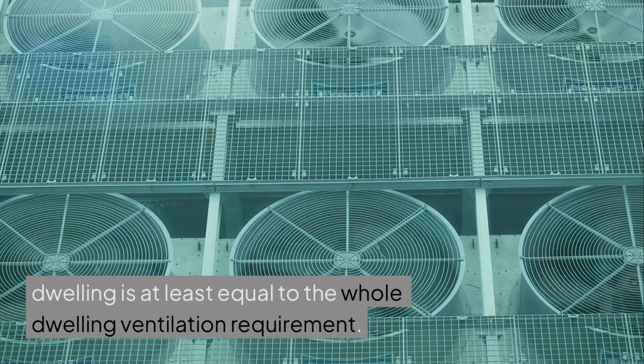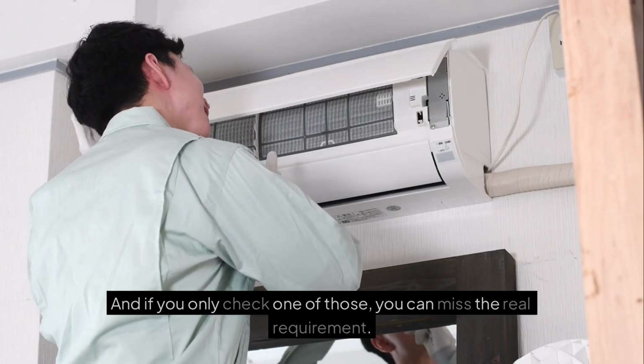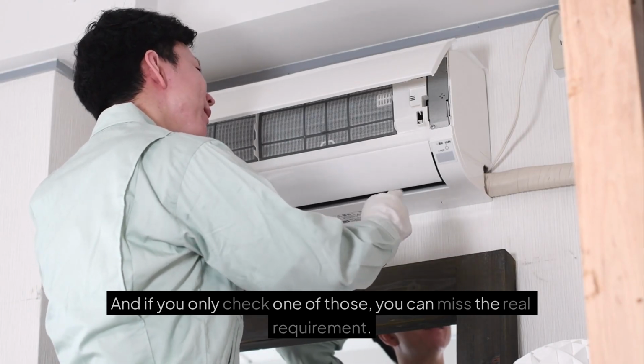That means continuous extract ventilation has two layers of thinking: local wet room high rates, and total dwelling continuous rate. And if you only check one of those, you can miss the real requirement.